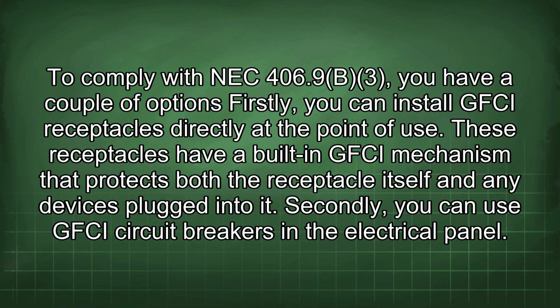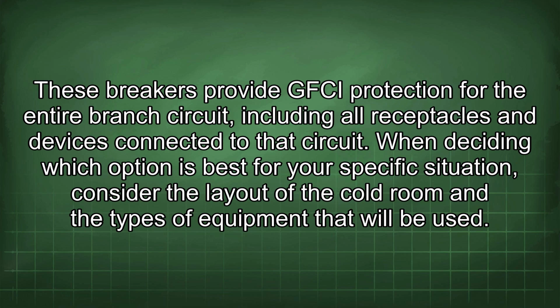Firstly, you can install GFCI receptacles directly at the point of use. These receptacles have a built-in GFCI mechanism that protects both the receptacle itself and any devices plugged into it. Secondly, you can use GFCI circuit breakers in the electrical panel. These breakers provide GFCI protection for the entire branch circuit, including all receptacles and devices connected to that circuit. When deciding which option is best for your specific situation, consider the layout of the cold room and the types of equipment that will be used.